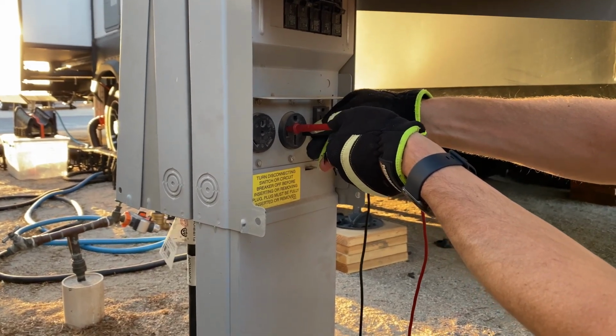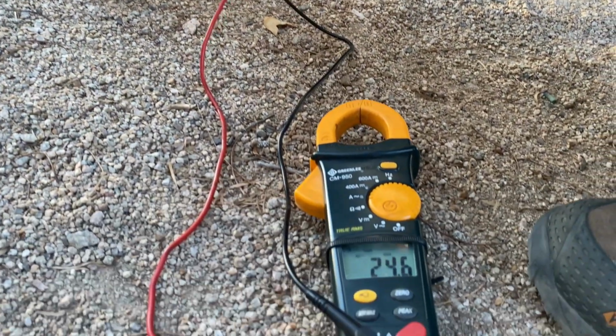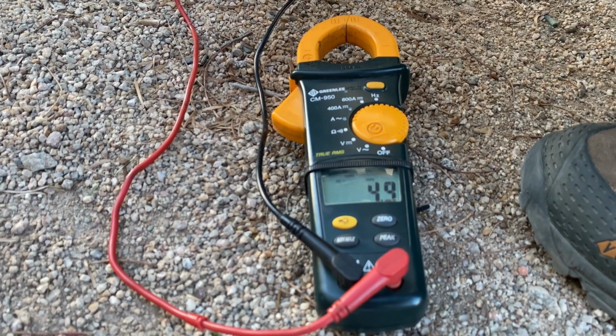I always check the pedestal to make sure that the power is right. I have 120 volts on each side of my 50 amp plug, my grounds and neutrals, everything is correct. But when I was checking the power, I noticed that one of the legs didn't have power, it wasn't quite right. I plugged a surge protector in without the RV hooked up, and it confirmed on my multimeter that one of the legs wasn't right.